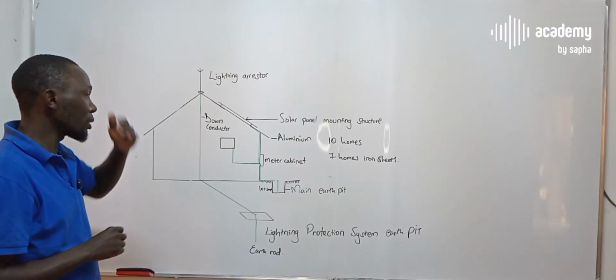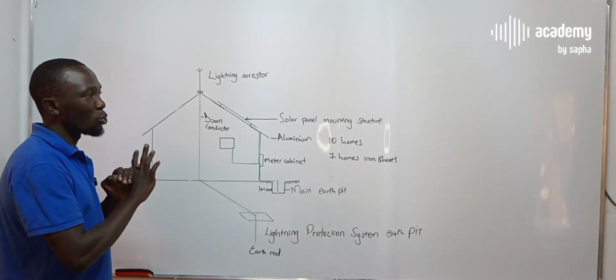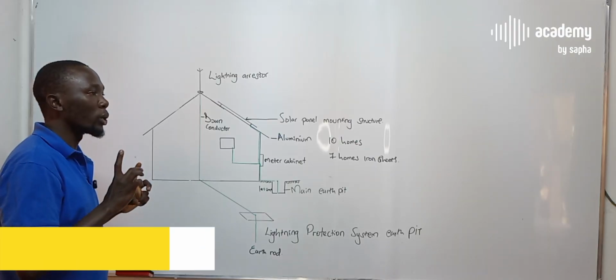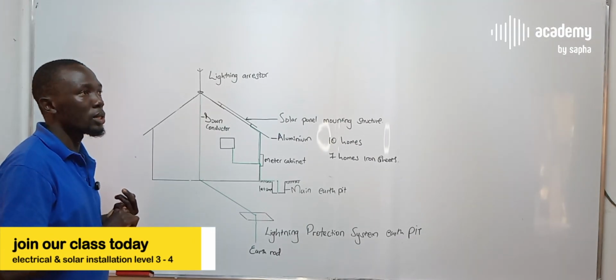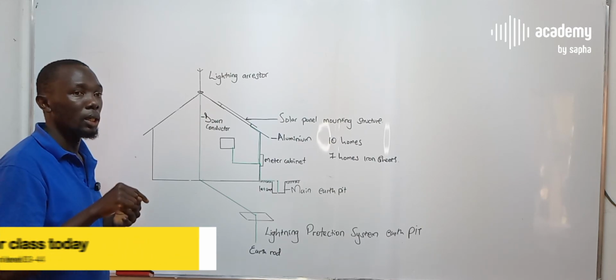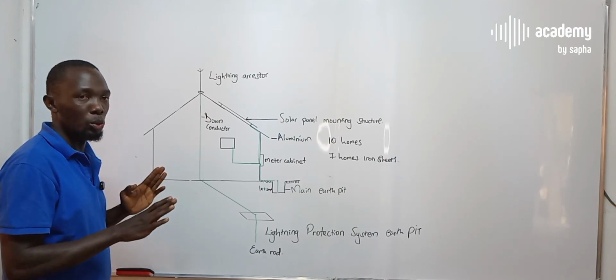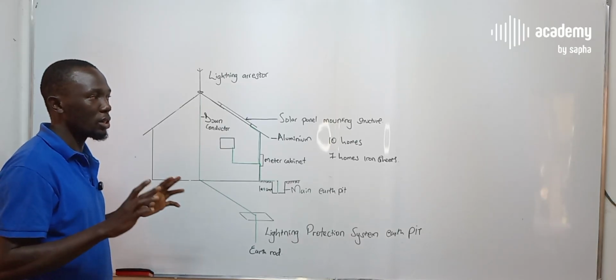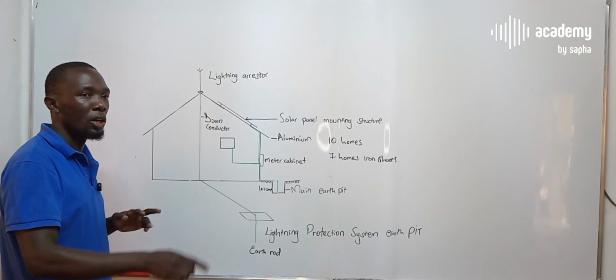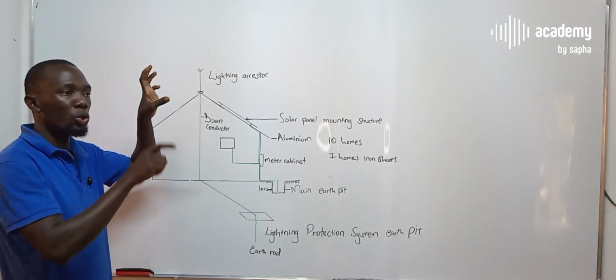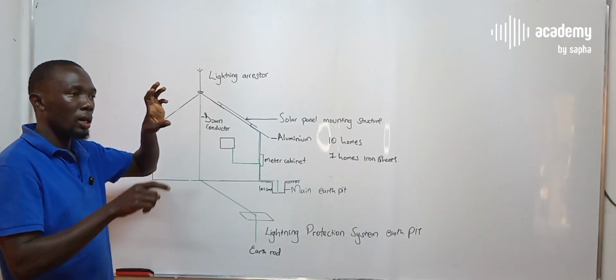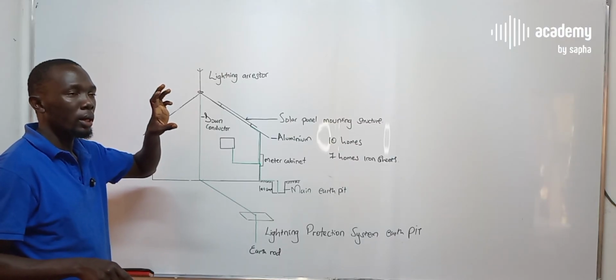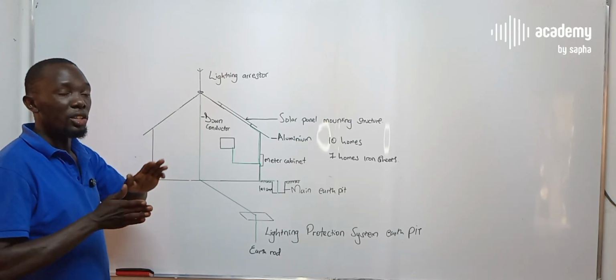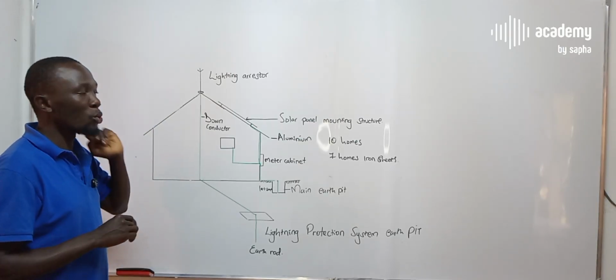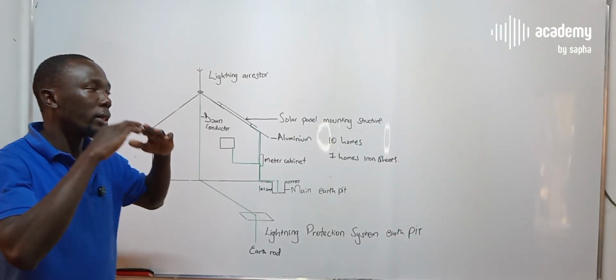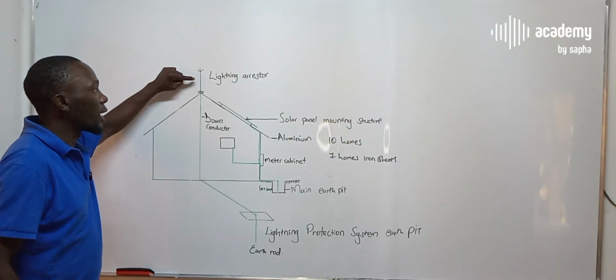Having that in mind, the IEC regulations - I'm not going to quote the numbers now, we shall be looking at those because I'm supposed to teach IEC regulations in module 3, starting January. So I don't want to quote them now. When reading regulations, they are normally a bit confusing if you go into one regulation straight. You're supposed to build from the base regulation, go to its alternatives, what we call recommended deviations if you have to deviate. So I don't want to send you to an exact regulation, but the IEC regulations demand that the lightning arrestor, this component on top of the roof, should be at a distance of S from any electrical or metallic structures.